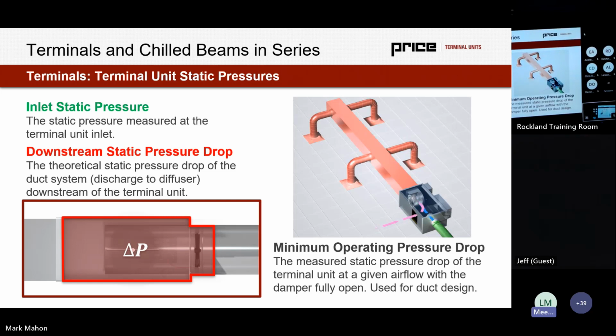So when we look at terminals, it starts with static pressure. Static pressure is what we're using for all of our duct design. So we're looking at static pressure drop across appurtenances within the duct, static pressure drop across the terminal unit.